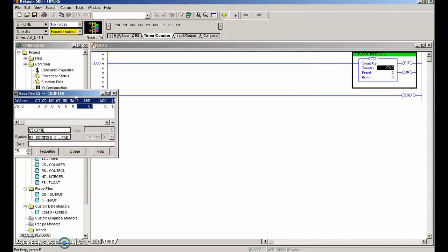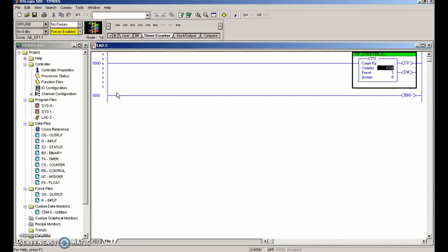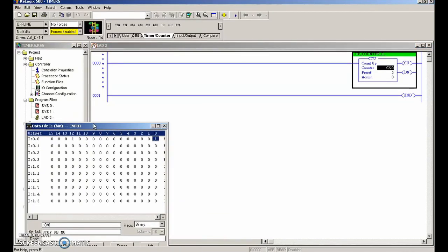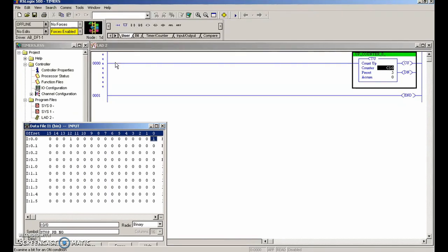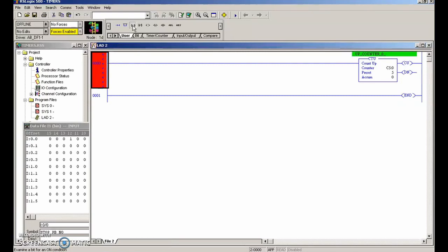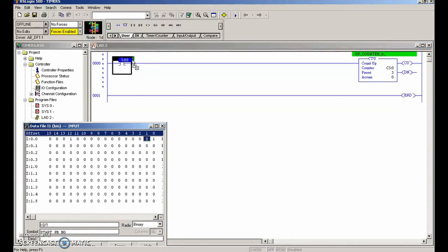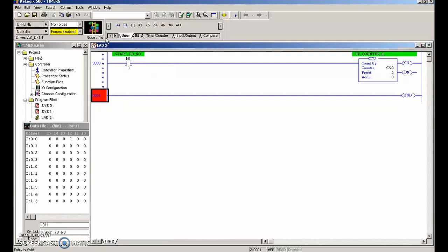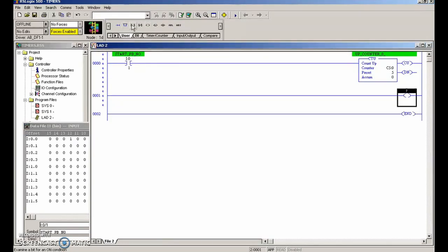We need something to fire that counter on. Let's put an input there and drop in an instruction. We're going to grab this rung, drop down an instruction, and that is going to be my start push button - input number one. That's going to do my up-counter, and then we need to fire on the bits that correspond to the up-counter. We're going to have one looking at the done bit and that's going to fire an output light.